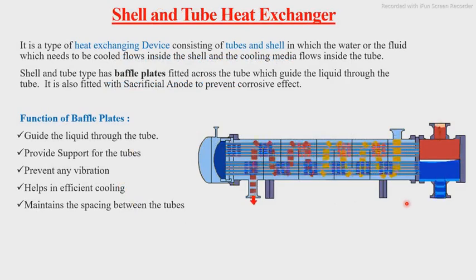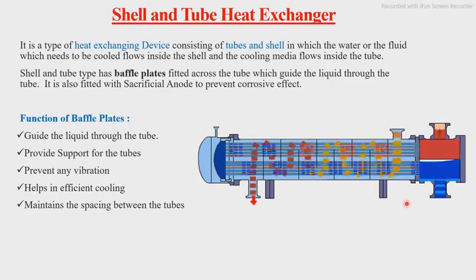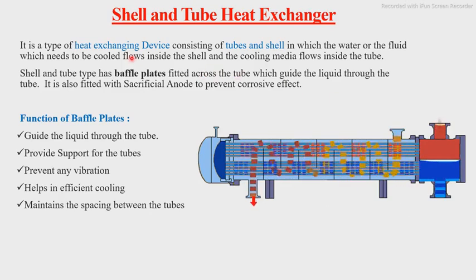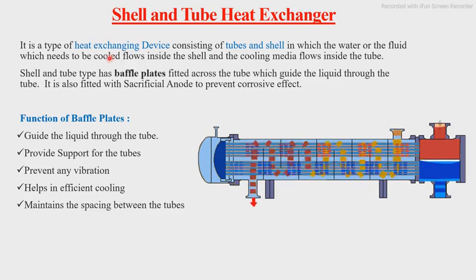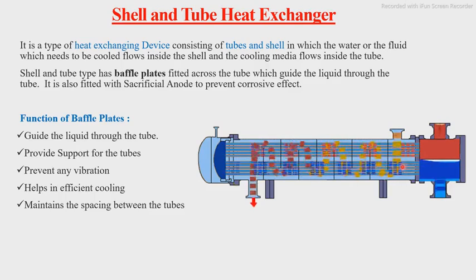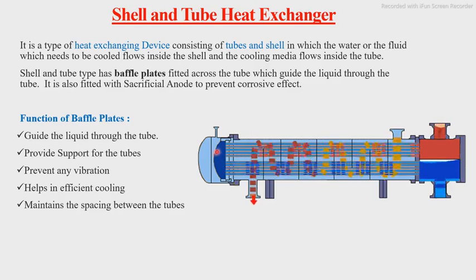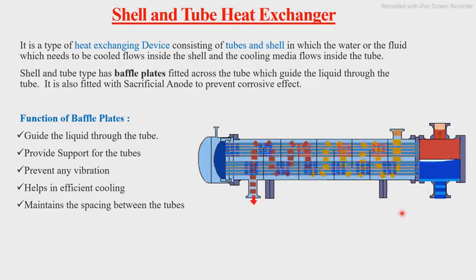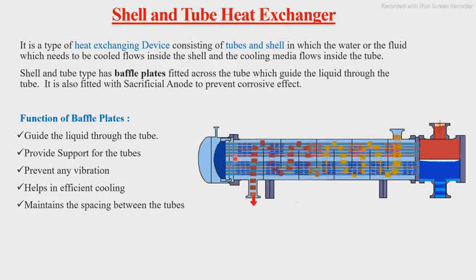The shell and tube heat exchanger is a type of heat exchanging device consisting of tubes and a shell, in which the water or fluid which needs to be cooled flows inside the shell, and the cooling media flows inside the tubes. The coolant enters cold, absorbs heat from the shell-side fluid as it travels through the tubes, and exits hot. The liquid being cooled enters from one side and exits the heat exchanger from the other side.